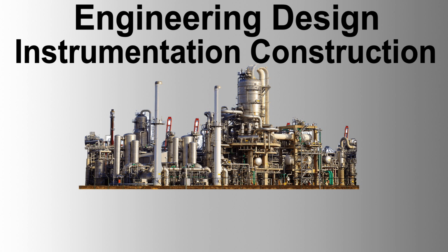All instruments shall be provided with the following identification means: stainless steel label provided by instrument manufacturer containing instrument details. Traffolite tag number to be mounted on the instrument stand. Black letters on white background shall be used for the control instruments and valves. White letters on red background shall be used for safety-related devices. Contractor to ensure all tapping points are in the correct orientation to keep the impulse lines as short as possible, at the same time enabling control instruments to be mounted as close as possible to their associated control valves.